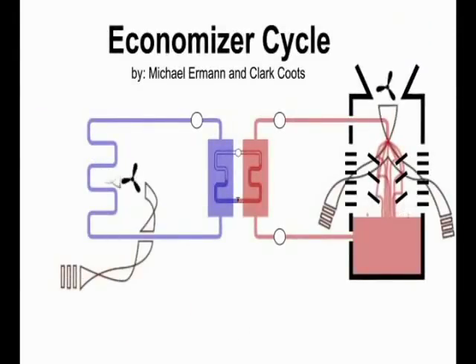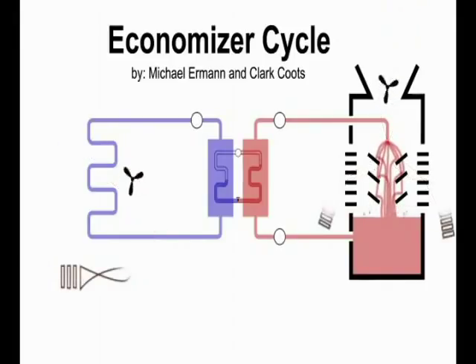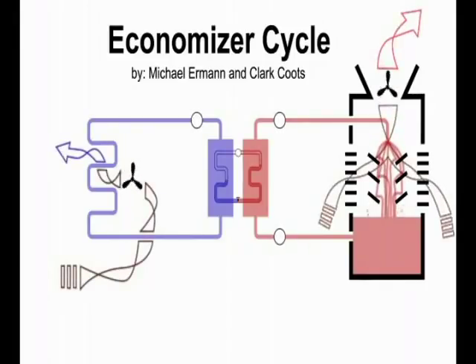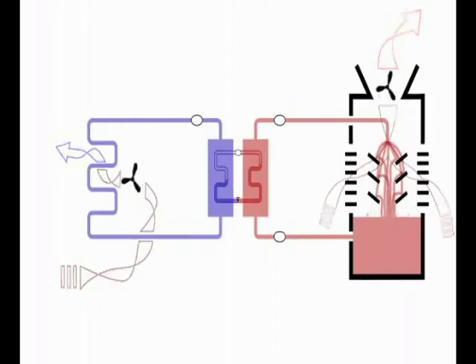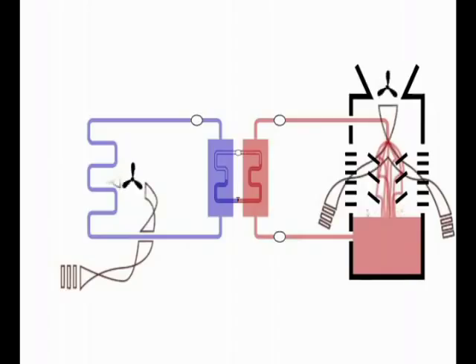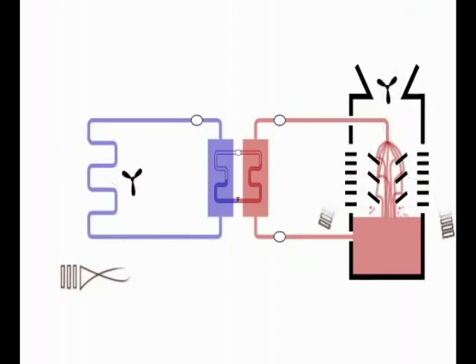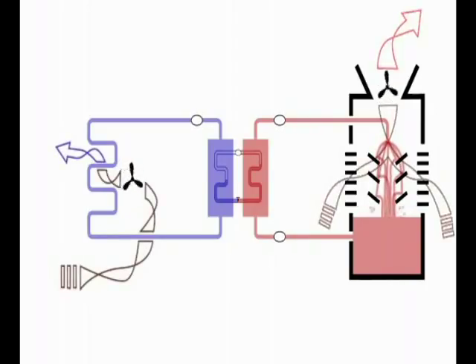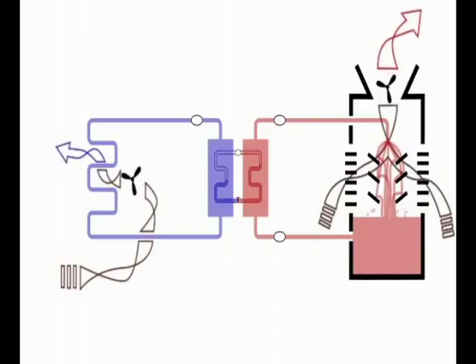Economizer cycle. Buildings, especially in the interior of large structures, often require mechanical cooling, even on very cold nights. This is because the heat generated inside the building by people, lighting, and equipment will offset some of the heat losses through the building envelope.